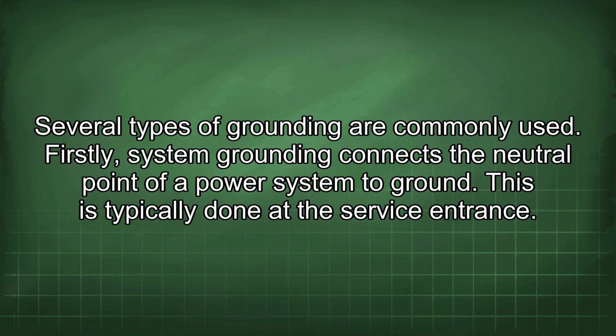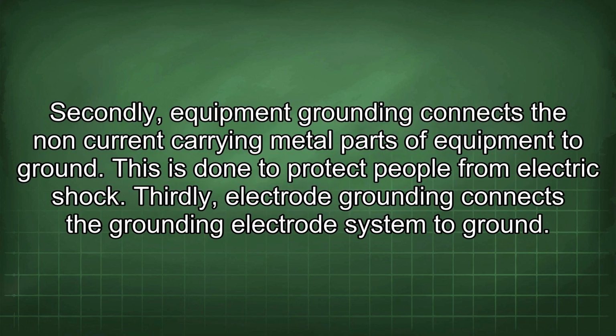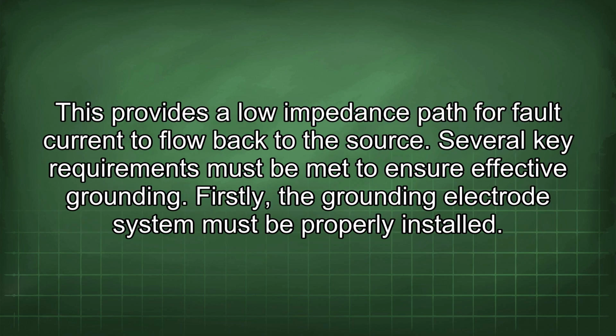Several types of grounding are commonly used. Firstly, system grounding connects the neutral point of a power system to ground. This is typically done at the service entrance. Secondly, equipment grounding connects the non-current carrying metal parts of equipment to ground. This is done to protect people from electric shock. Thirdly, electrode grounding connects the grounding electrode system to ground. This provides a low impedance path for fault current to flow back to the source.